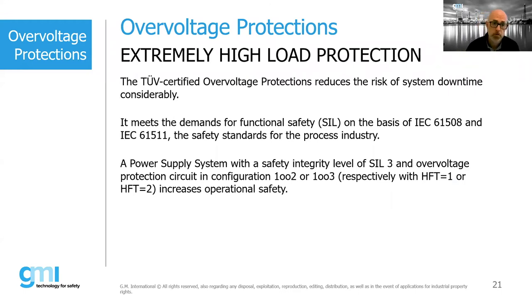Yeah. Overvoltage protection, as mentioned above, is fundamental in a safety power supply system because it allows us to reduce the risk of system downtime considerably. In fact, if one of the safety power supplies fails in an overvoltage condition, the protection brings the output to 0 volt, allowing the other safety power supply to continue working correctly without the risk of sending the system to shutdown.